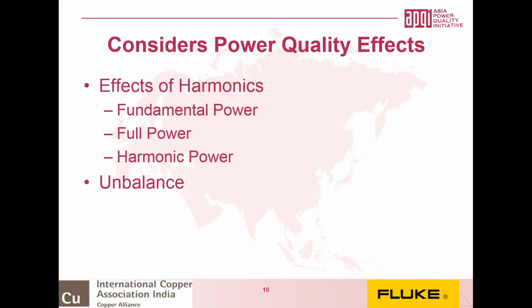So it may well be that harmonics on the system are the biggest problem, in which case you don't need to mitigate for unbalance, or it may be the other way around. But understanding exactly where the losses are coming from enables you to intelligently decide whether the return on investment for installation of filters or other compensation devices is worthwhile. If you can quantify what the losses are and you can see how much that costs over time, then it makes the investment decision that much easier.